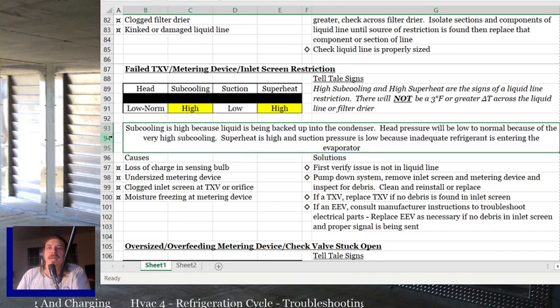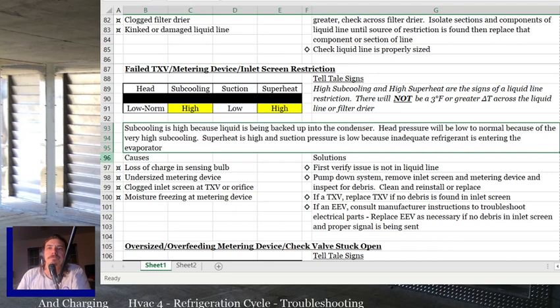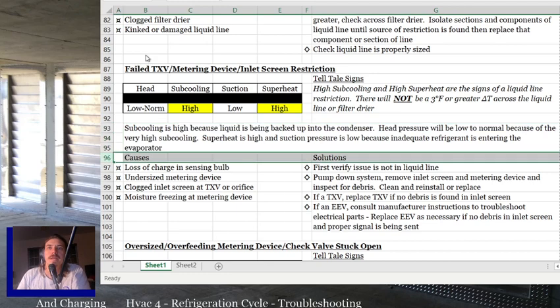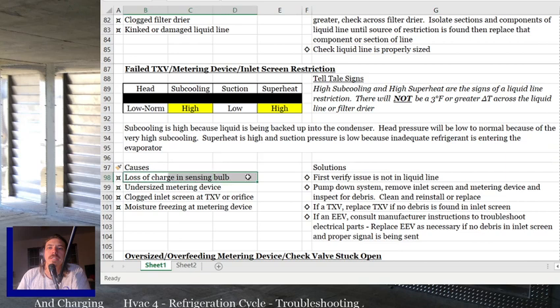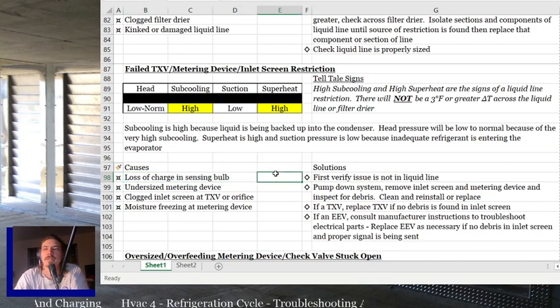So that is what that is. The causes of that are loss of charge in the sensing bulb, which will cause a TXV to close completely up, and it causes a liquid line restriction. An undersized metering device: you're supposed to switch out the metering device when you need to. When you've got a piston, you need to make sure the piston is matched to the outdoor coil. If the piston is the wrong size, then it will act as a restriction.